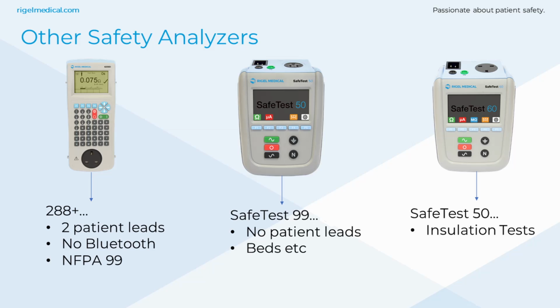It's just via a USB connection, and it only tests to local standards like NFPA 99, but it also does IEC 62353. So it's not going to be able to perform any tests, or at least not all of the tests, to IEC 60601. So that's a slightly cheaper device than the 288, but it comes in at a better price factor, but it doesn't have as many functions as the 288.